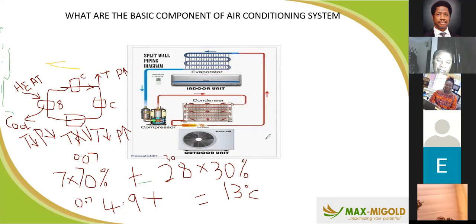Once you start the compressor, there's an oil that melts inside that allows free flow of refrigerant. Like engineers know, you don't allow rubbing - if you rub iron to iron together, the surface becomes hot. So if gas alone moves inside the copper pipe, there's every tendency it will be very hot. To create smooth operation, oil made for that refrigerant gas is introduced inside the compressor for easy movement. So when it ruptures at a particular point, that oil actually bursts out.